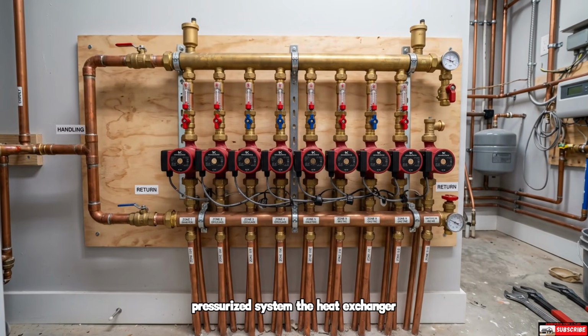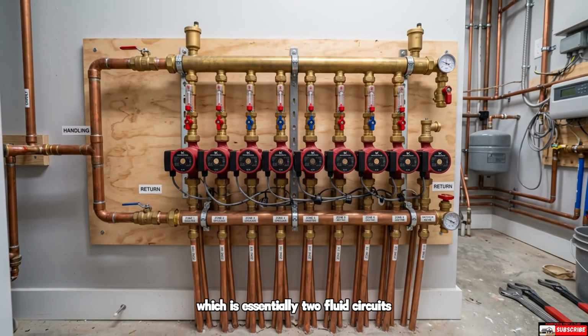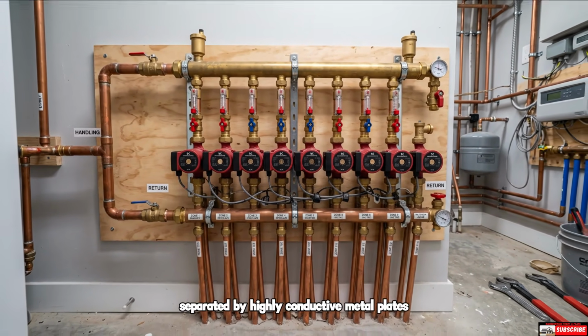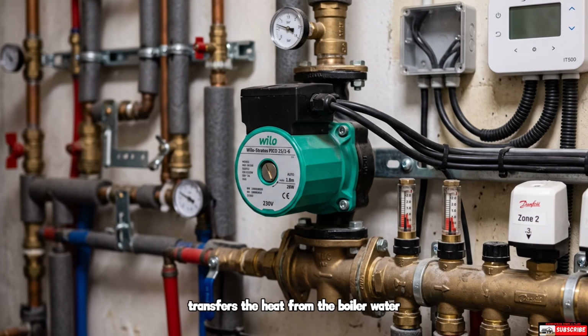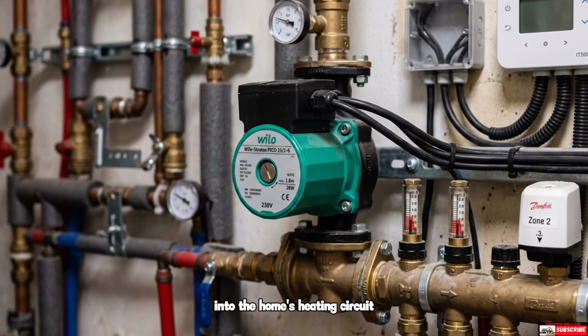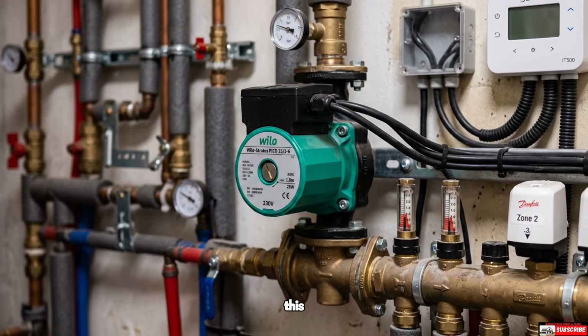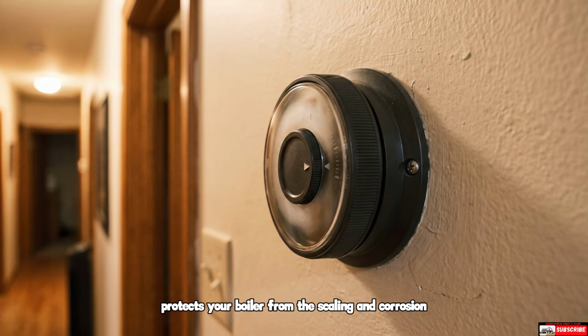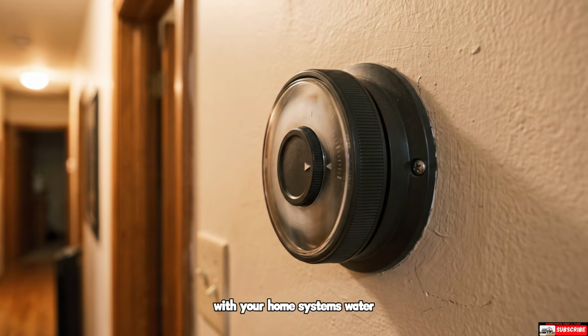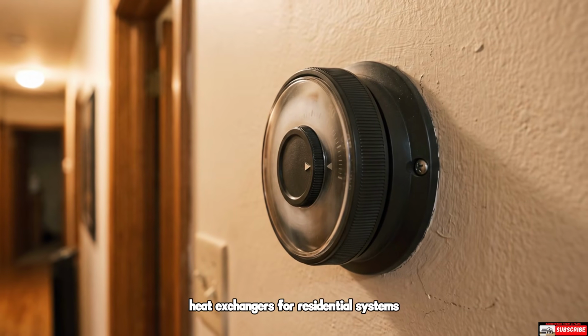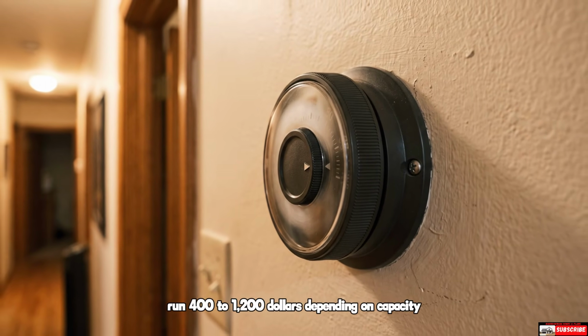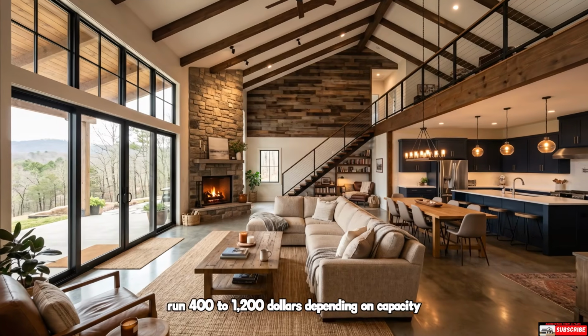The heat exchanger, which is essentially two fluid circuits separated by highly conductive metal plates, transfers the heat from the boiler water into the home's heating circuit without mixing the two fluids. This protects your boiler from the scaling and corrosion that would come from constantly mixing with your home system's water. Heat exchangers for residential systems run $400 to $1,200 depending on capacity.